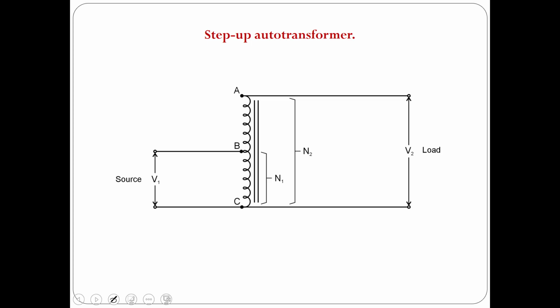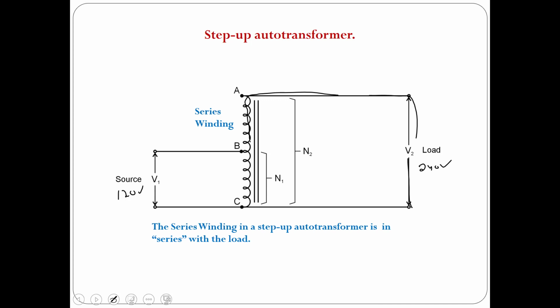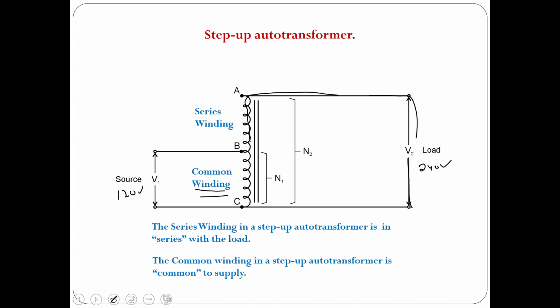Here's a picture of a step-up autotransformer. And so in this case, we'd have our lower voltage coming in. We could say it's 120 or something like that. And we'd put out a voltage of, let's say, 240, something like that, or better. All right. So to look at this, we have to identify parts of this autotransformer. So one is the series winding. On a step-up autotransformer, the series winding is the one that is in series with the load. Okay. And so the series winding in a step-up transformer is in series with the load, whereas the other part of this winding is the common winding, and it is common with the supply or the source.